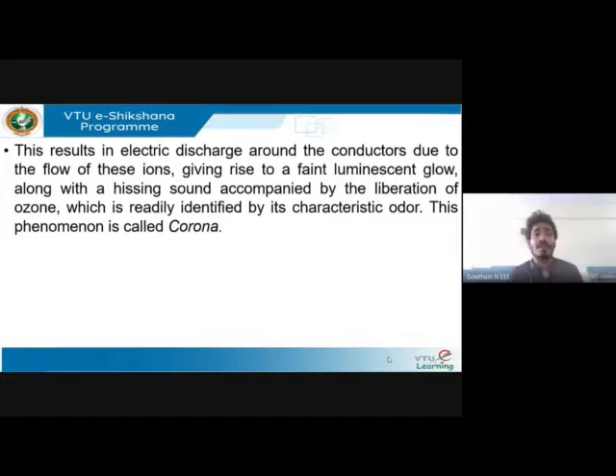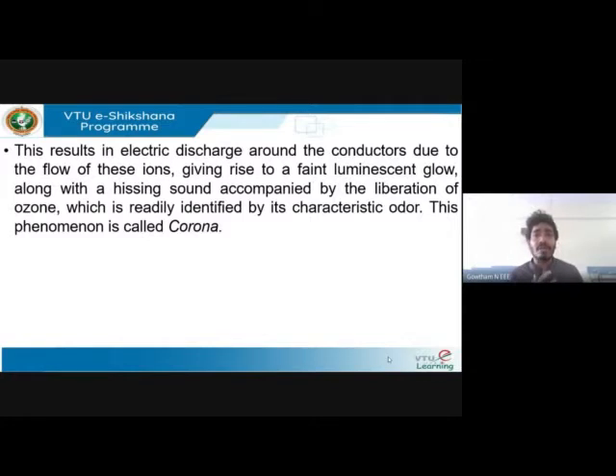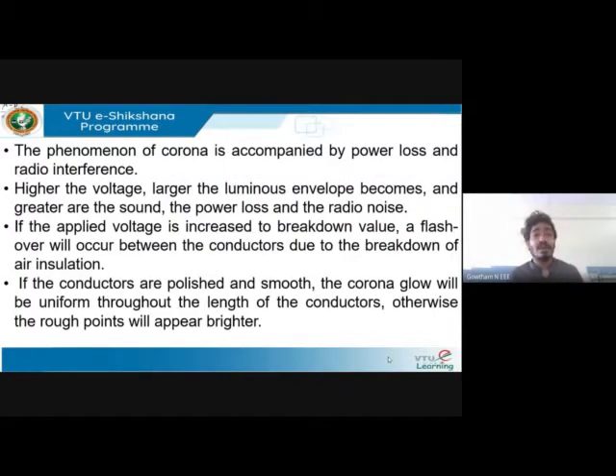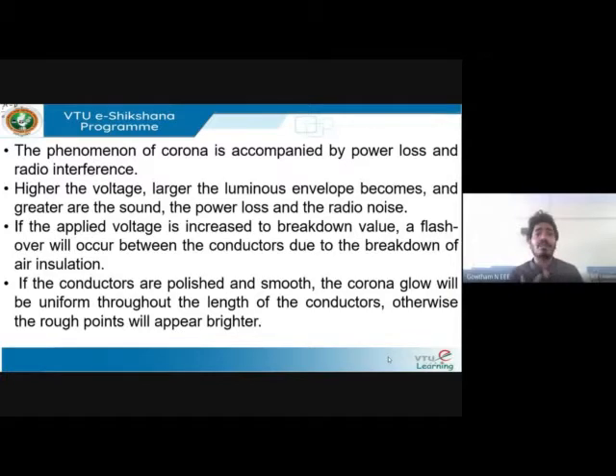Because the surrounding air also becomes conducting as electrons come out due to the increased potential gradient, you get an electric discharge called corona. This is a faint luminescent glow accompanied by a hissing sound. As a consequence of corona, there will be power loss and radio interference. If you increase the voltage even higher, you'll have a larger luminous envelope with more sound and more power loss.